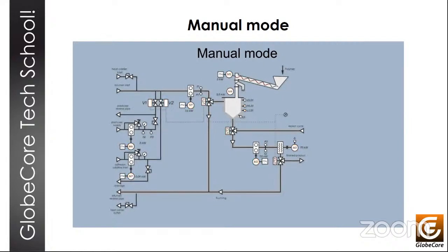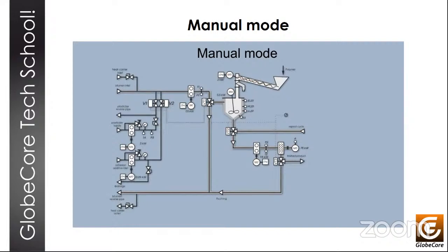So, emergency stops: when any alarm occurs, the machine stops, and the alarm off button lights up. There is a light and sound alarm that is turned on. A corresponding message appears on the controller screen. And the operator can just briefly press the alarm off button to turn off the siren.